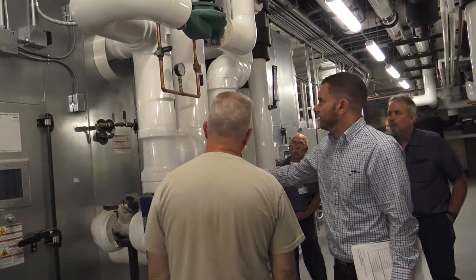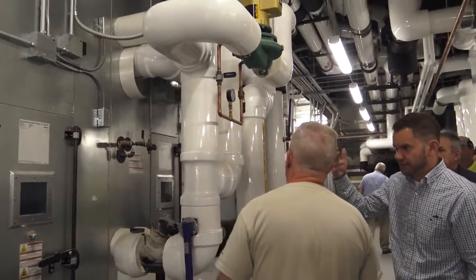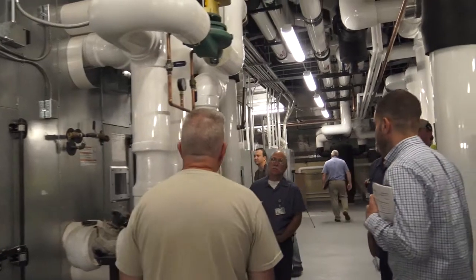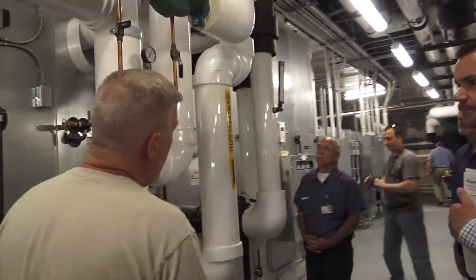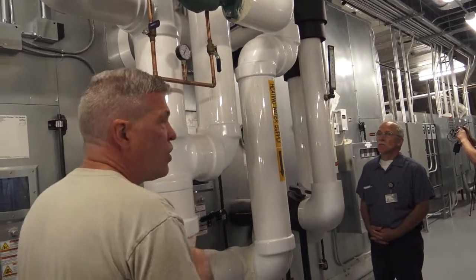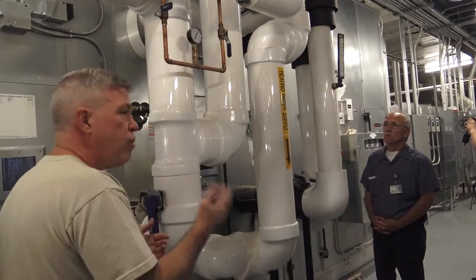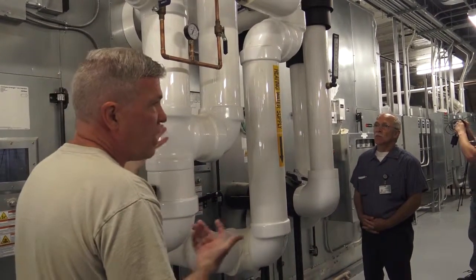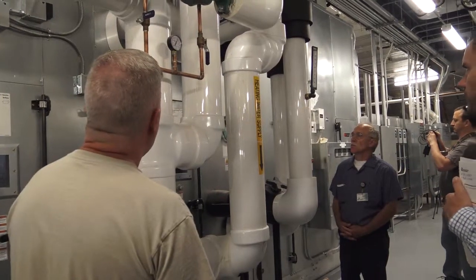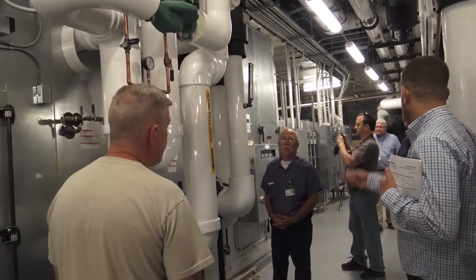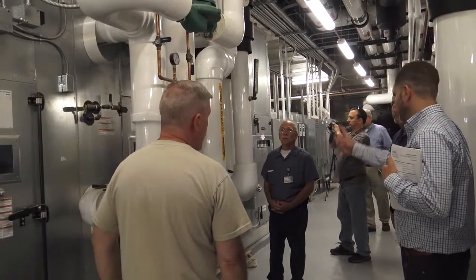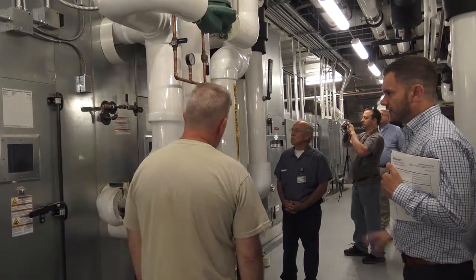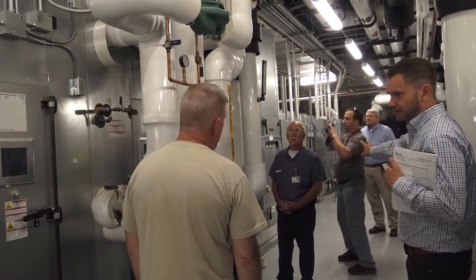Right now there wouldn't be. This is not active at all, right? Because the outside air is 70 degrees. Right. Yeah, they'll kind of switch over. Right now it's like 50 degrees is the switch over. So above 50, we use chill water. Below 50, you're kind of switched over to reheating, hot water. Right, nighttime, this is running right now, and then daytime, we're cooling the water there. Because it's always leaving the air handler at 55 degrees or thereabouts.